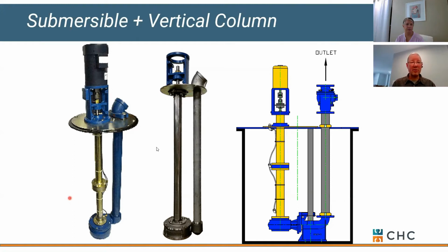One of the other issues we see, and by the way, thank you everybody for taking part of that poll. One of the issues we see with vertical column is that the column or the shaft length has to be as long or as deep as the basin. So if you've got a 10-foot basin, you've got a 10-foot line length. And a lot of those will have intermediate bearings or lubrication spots. And if that doesn't get maintained or lubricated, now you get a shaft that starts to wobble or gets out of control. You can get a lot of very rough vibration up near the surface.